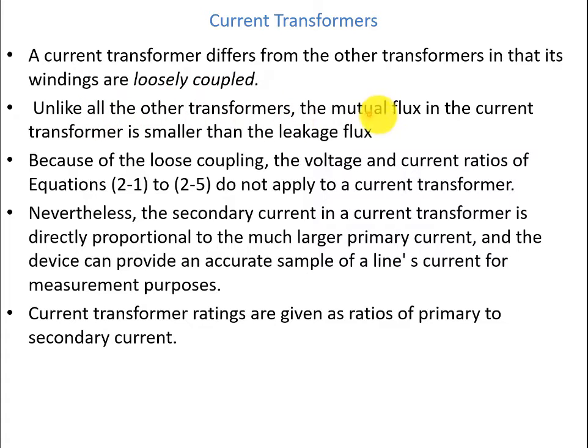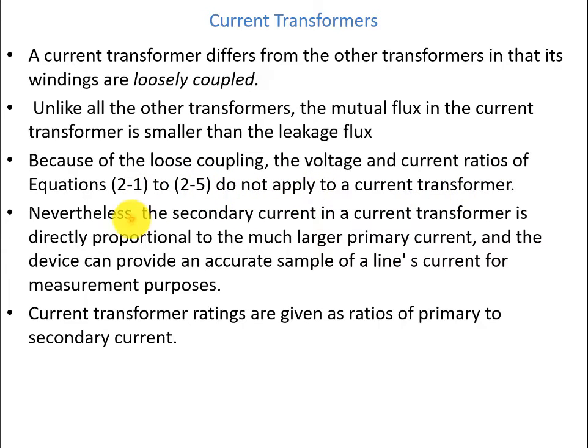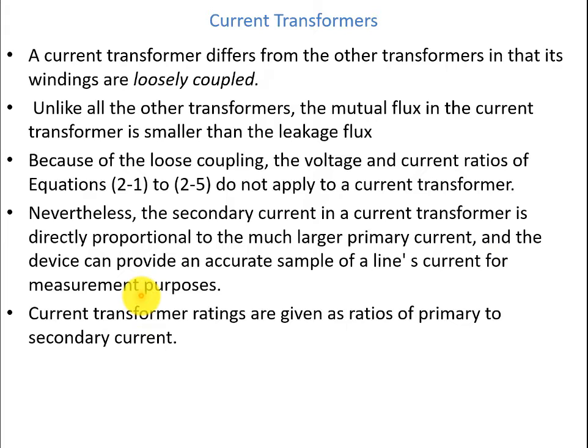Unlike all other transformers, the mutual flux in the current transformer is smaller than the leakage flux. Because of the loose coupling, the voltage and current ratio equations we have seen previously do not apply to the current transformer. Nevertheless, the secondary current is directly proportional to the much larger primary current, and the device can provide an accurate sample of the line's current for measurement purposes.